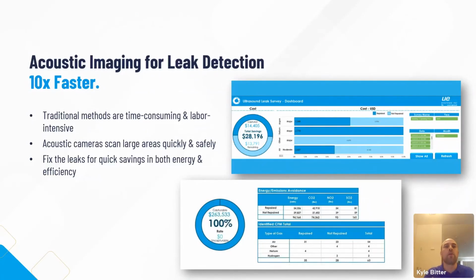With the use of acoustic imaging cameras, we have the ability to scan large areas quickly and safely. The SI2 Pro camera, for example, has a detection straight line distance of 656 feet. We don't necessarily teach standing 600 feet away from a leak when trying to quantify it, we want to get as close as possible, but it's good to know you have great detection distance so you can always stay at a safe distance.